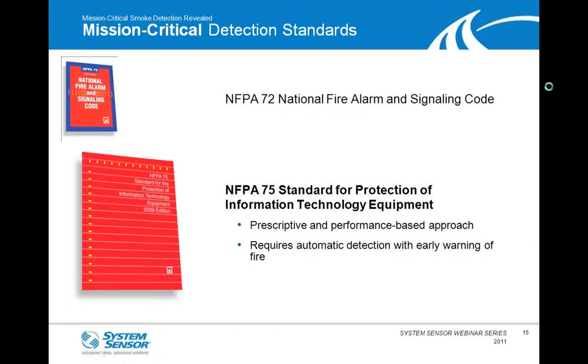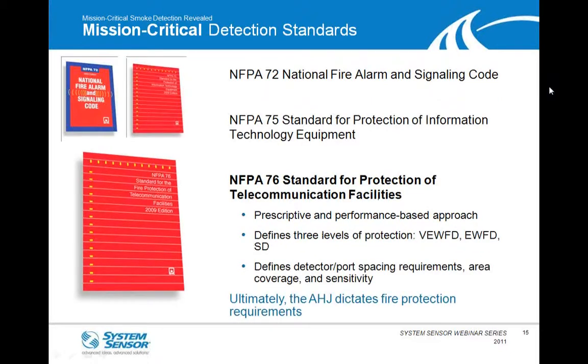that allows people to evacuate. And then finally, the third one that we'll talk about is NFPA 76, the Standard for Protection of Telecommunication Facilities. And this is the one I always talk about that starts to get a little bit more detailed, in that there's 3 levels of protection, and I'm not going to really go into those too much now. We'll get into it later. And then also the coverage area as well as transport time if aspiration detection is used. And again, for all these standards, ultimately the AHJ dictates fire protection requirements. It's kind of our standard saying, but it does hold true in every jurisdiction.